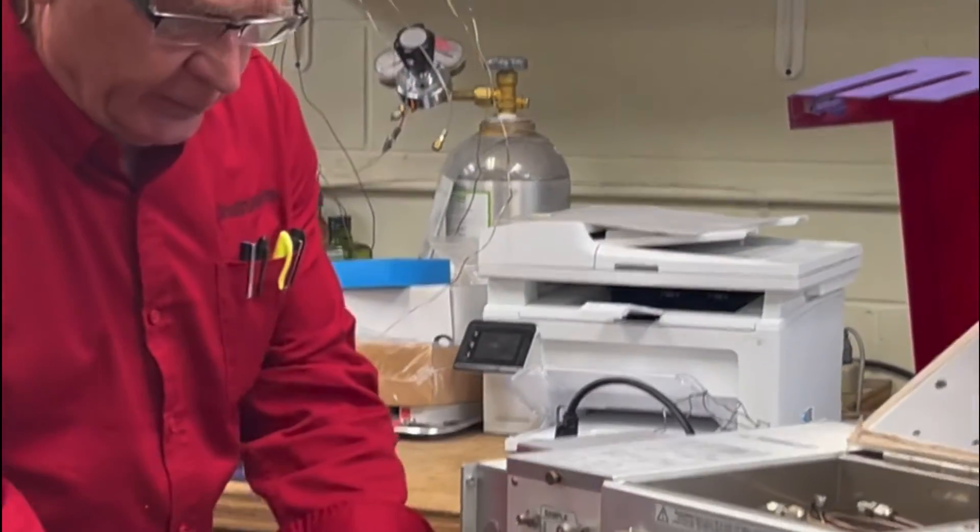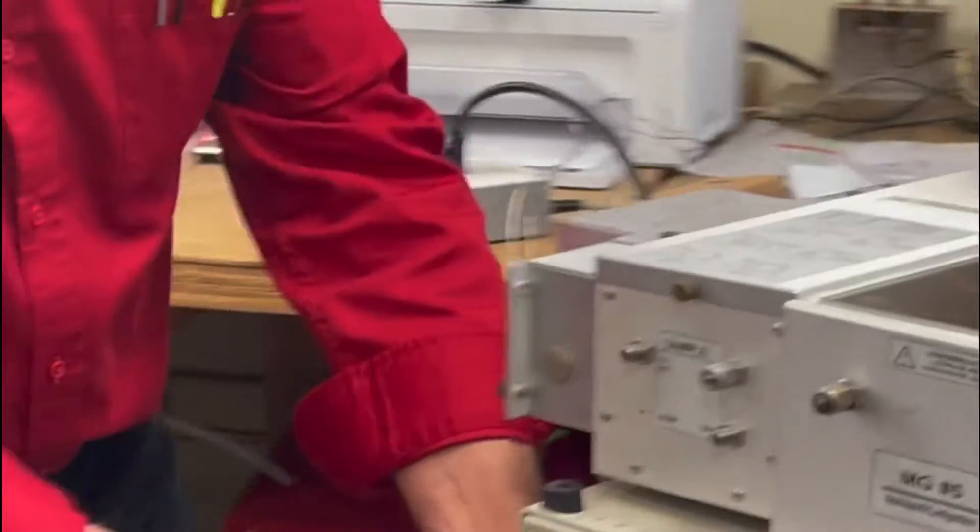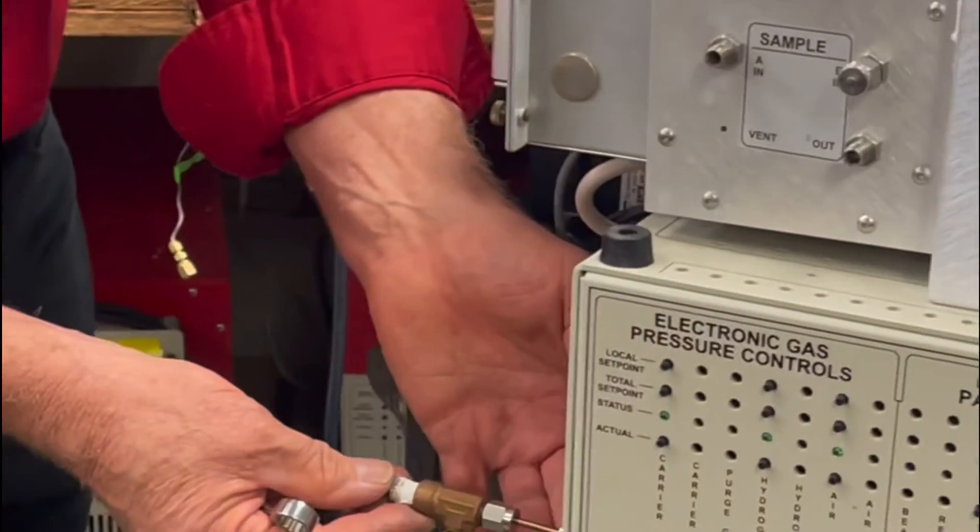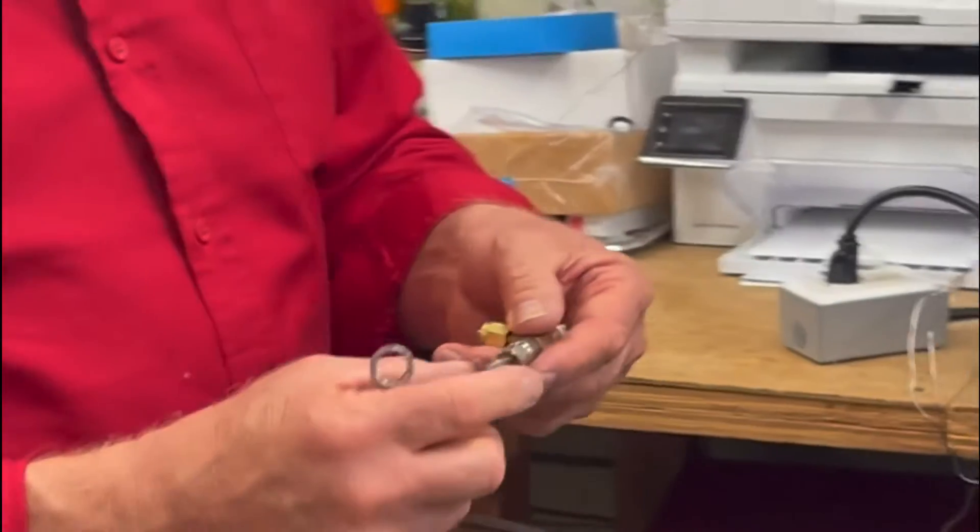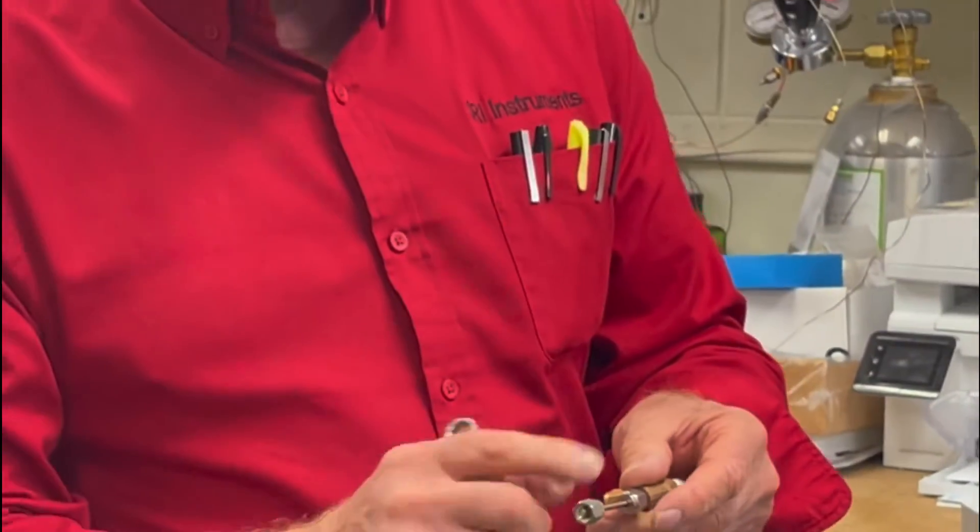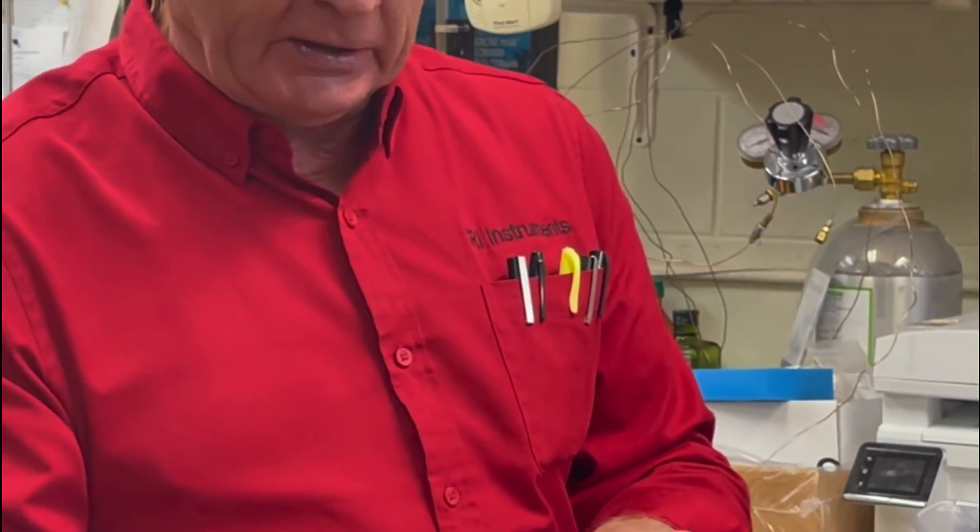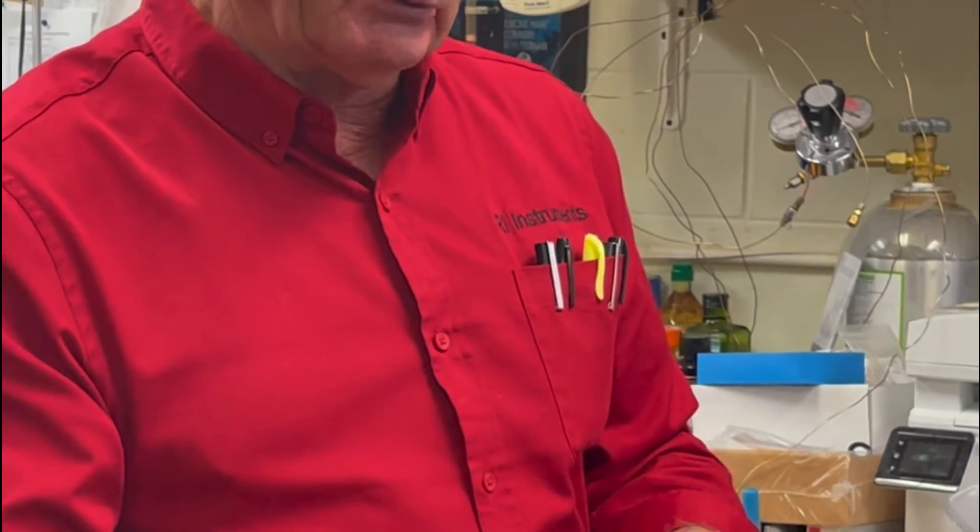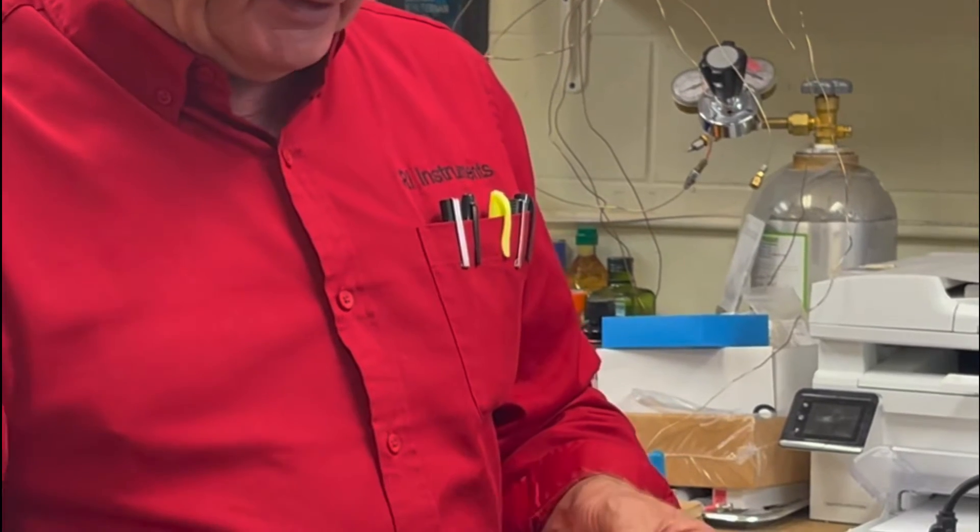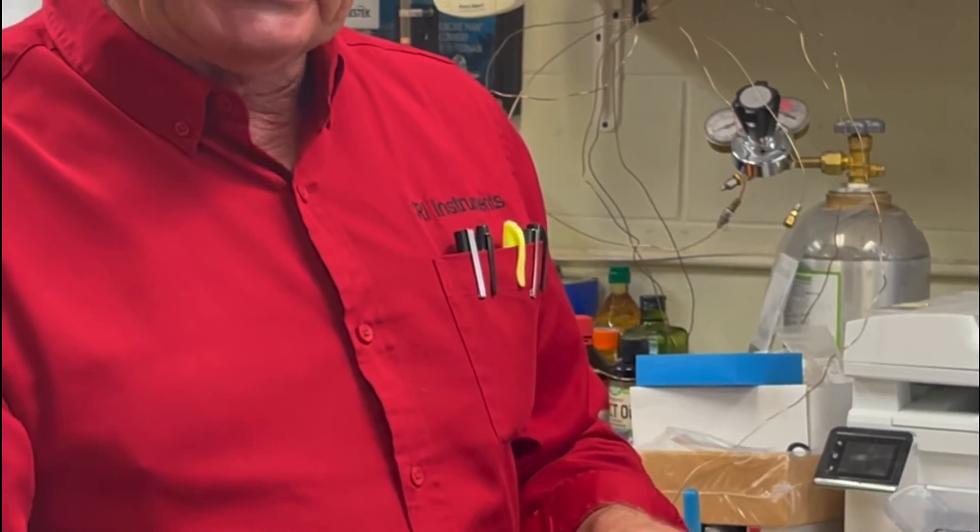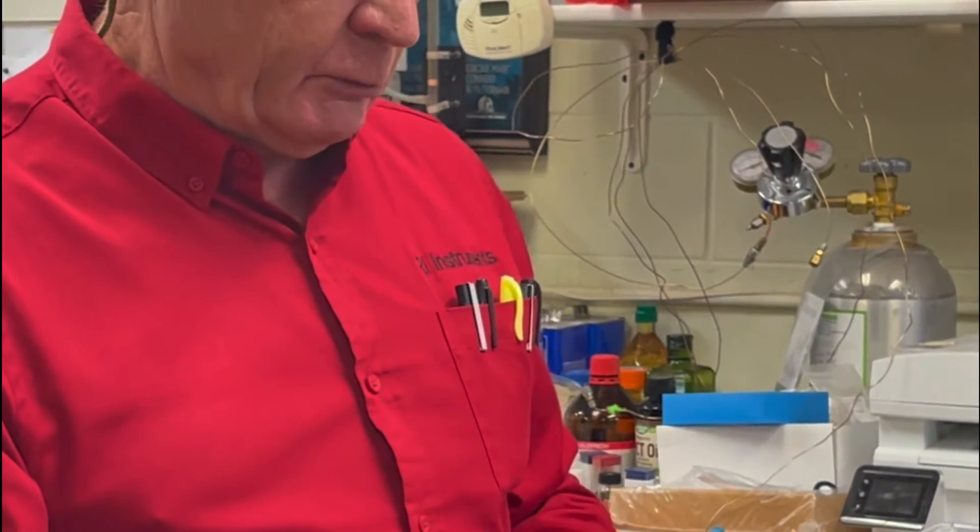This size of tubing, the eighth inch tube, is used in various places around the GC including where the gas gets connected to the GC on the outside. It's really not necessary to have stainless steel tubing because stainless steel tubing is very difficult to cut unless you have a special tool which is five, six, seven hundred dollars for an abrasive cutoff wheel. And when you cut things off abrasively it makes dust and dust is what we're trying to avoid.